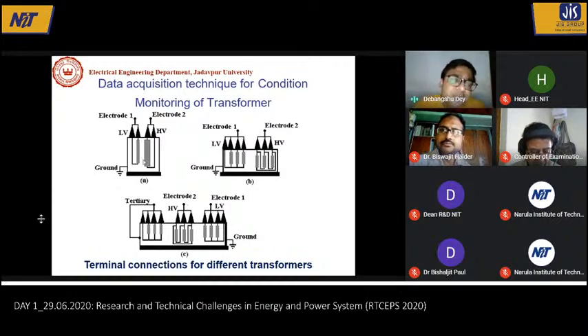If we are trying to find out the condition of the transformer, we are mainly interested in the condition of the insulation of the windings. So if we take electrode 1 and electrode 2 as the two plates of a capacitor, the insulation will be in between these two electrodes. If we give some voltage across this, there will be some charging.